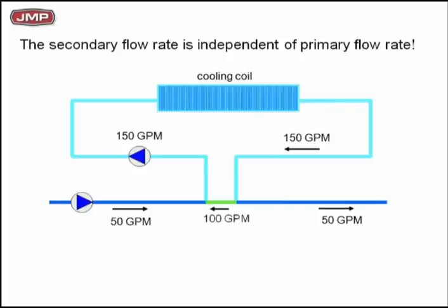So now you've been through all the examples of the good Lord's T-law. What goes in a T has to come out. And if you keep the pressure drop in the common pipe down to 0 or nothing, it has no impact on the flow rate of the secondary totally. What changes is the direction and the amount of flow in the common pipe.